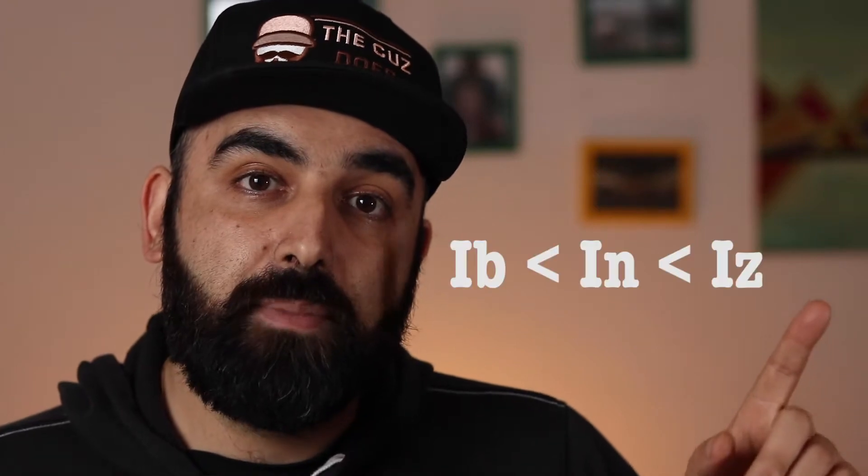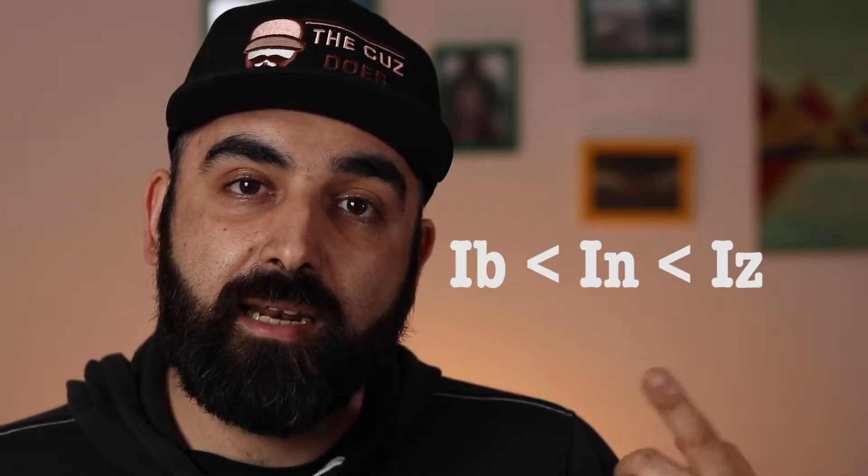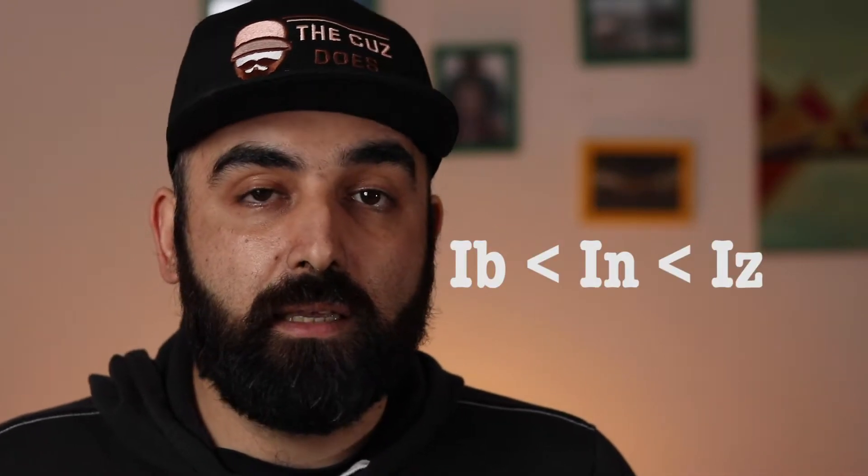But before we get into that, I need to explain something that you need to know about the wiring system. To dimension properly a wiring system, the only thing that you need to know is one law: IB lower than IN lower than IZ. Where IB is the current of your load, IN is the limit current of your safety switch, IZ is the current that your wiring can support. But we will go deeply into each of these arguments in a while.